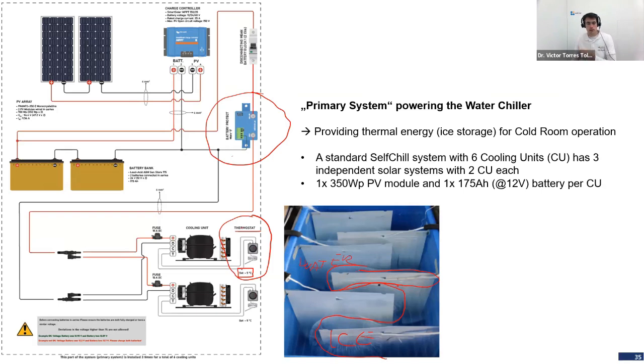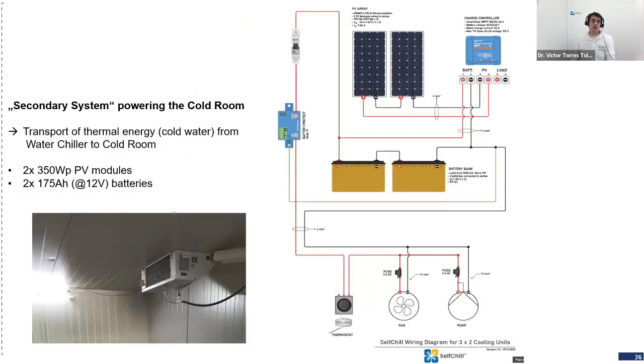Okay, so we understood we have thermostats that stop the cooling units when the ice storage is full, because we don't want to overfreeze the whole water chiller. Okay, let's go ahead. Now let's have a look at the secondary system. The secondary system is a separate solar system with PV panels, charge controller, and batteries, and then we connect a fan there. It's the fan inside the heat exchanger that delivers cold air. We have the water pump, and then we also have a thermostat.